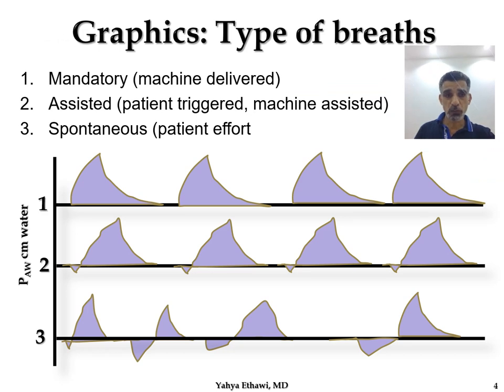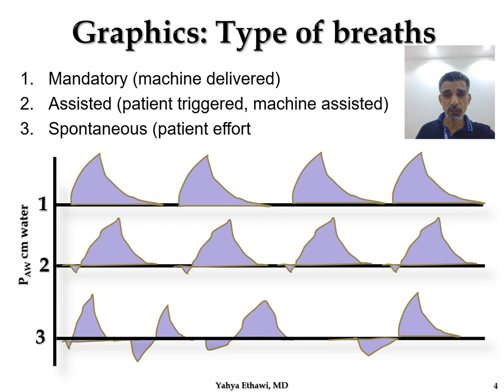There are three types of pressure waves. In the first line, we have beautiful waves with a good rising time, a short plateau, and a descending time — indicating good airway behavior. There is a pause between breaths, and they are all the same shape, so I know this is a mandatory breath provided by the ventilator.